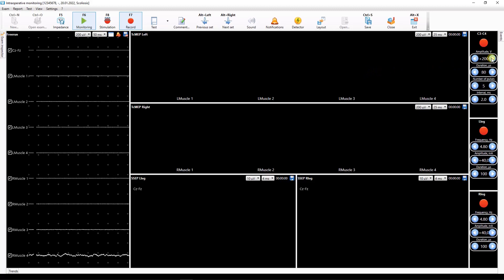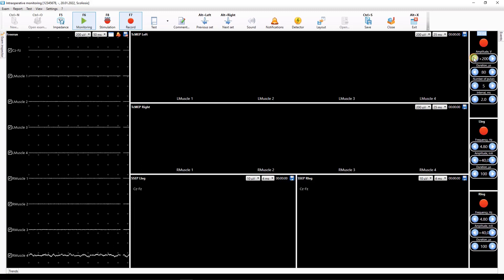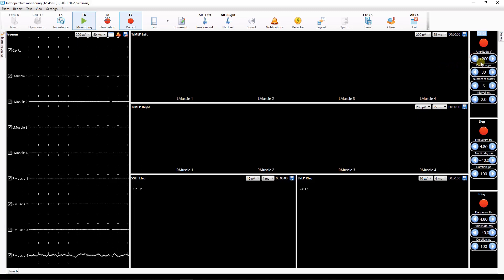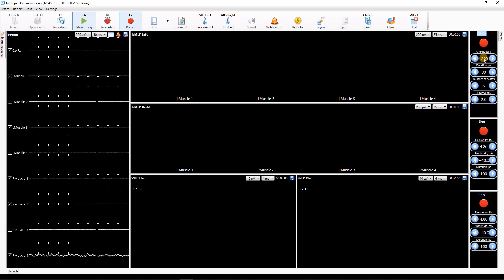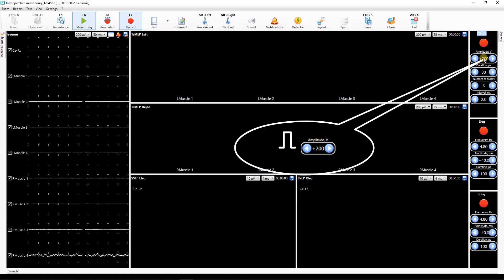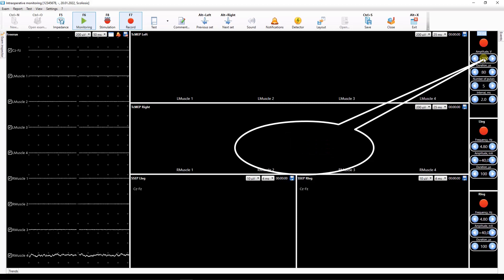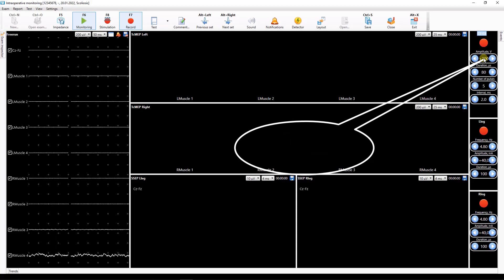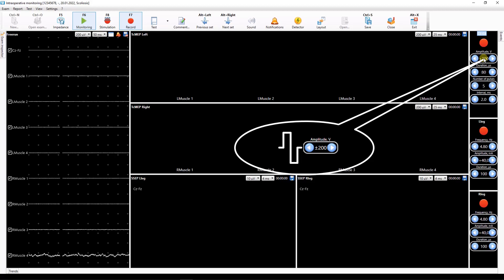Press the arrow buttons to increase or decrease the parameter values by one step. To quickly change stimulus polarity double click on the stimulus amplitude value. The plus symbol indicates normal polarity. The minus symbol indicates inverse polarity. And the plus minus symbol indicates biphasic stimulus.